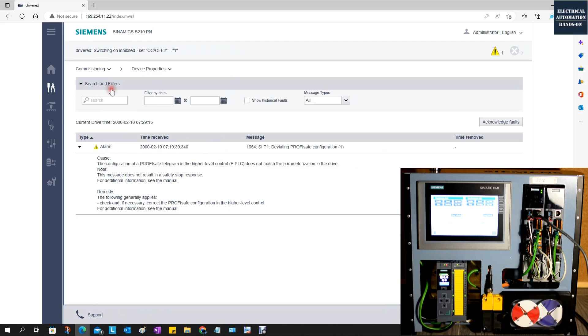Okay, then let's go to the commissioning. And we can go to the drive properties. And here we can see, you can set the device name. This drive has one preset name, drive read. I won't change it because, as we can see from the video, this servo drive at the left side is connecting with the right motor. So it is named drive read. And here we can set the motor rotation. In case the motor direction or the mechanical direction we define as forward does not match the direction, we can reverse this setting, counterclockwise or clockwise. Okay, so we can leave the default here.